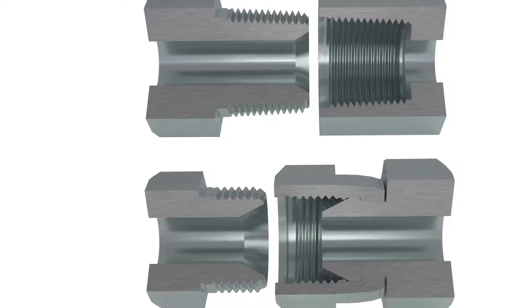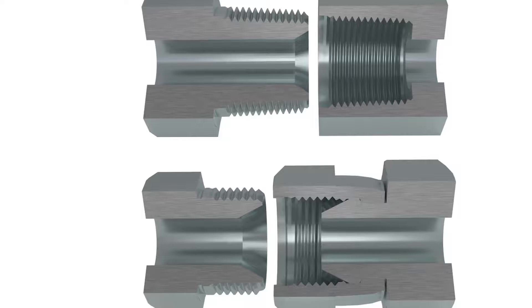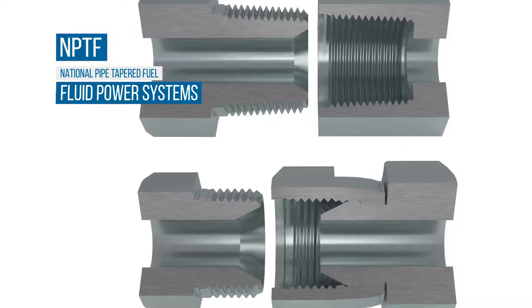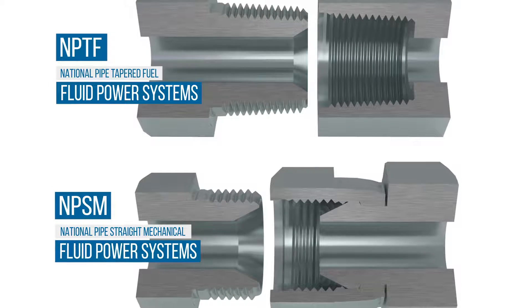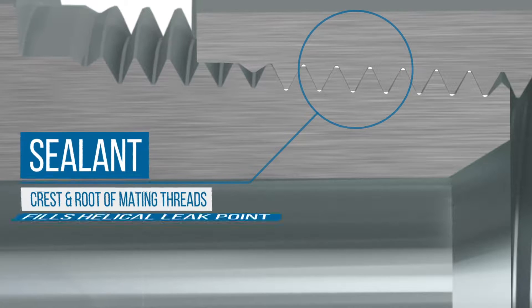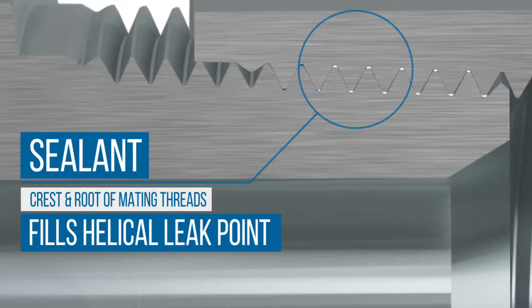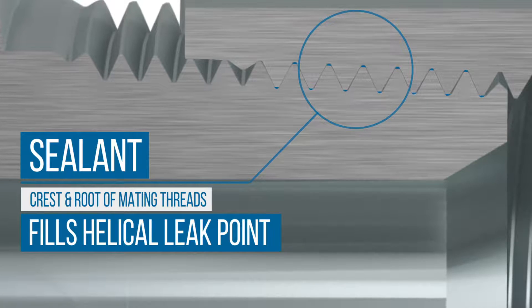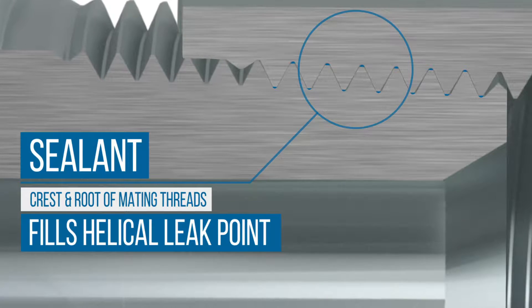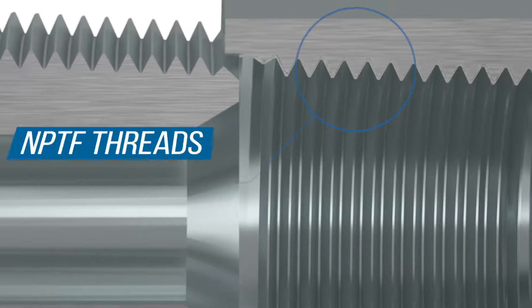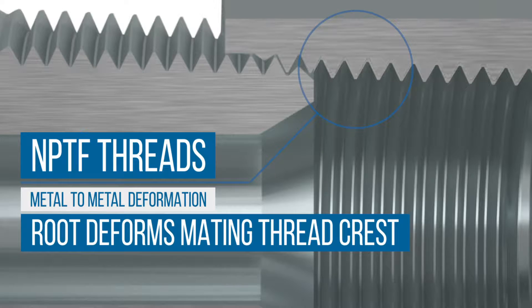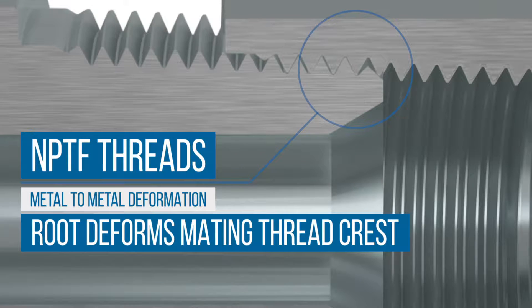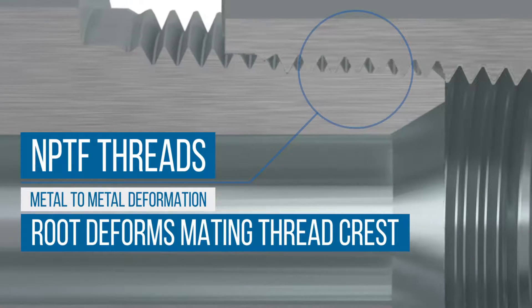Two of the most common variations of this pipe thread standard are NPTF and NPSM thread styles. Where traditional NPT threads have a small clearance between the crest and the root of the mating threads, requiring the use of sealant, the NPTF thread root does not allow this clearance. It contacts and deforms the mating thread crest.